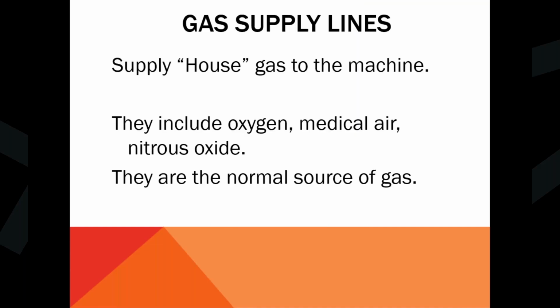Some of the other things that are part of the machine that you might run into if you're working on one or get called up to one: the machines all have gas supply lines that normally hook up to the house gas, the stuff that's built into the booms or the walls. They include oxygen, medical air, and nitrous oxide, and they are the preferred or normal source of your incoming gas.